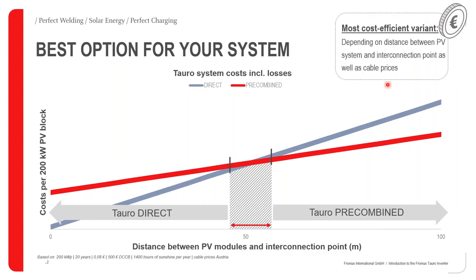So, as a conclusion, we can say that the most cost-effective variant will depend on the distance between the PV system and the point of interconnection, as well as cable prices. In summary, use the direct version in a situation where you have shorter distances from the PV array to the inverter. If you have the opposite, facing long distances from your PV array to the inverter, we do recommend the pre-combined version.